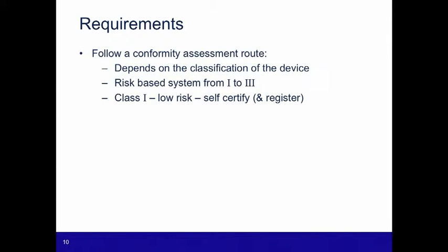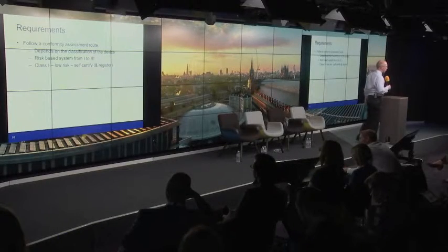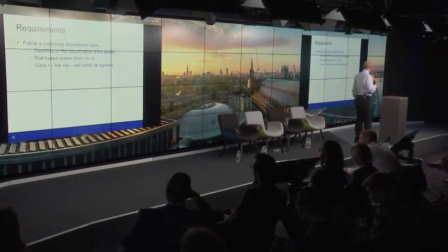Class 1 devices are considered to be low-risk devices, and there's a very light touch regulatory approach to this. You, as a manufacturer, self-certify that you meet all of the requirements. You register with us as a manufacturer, and that's all you need to do.